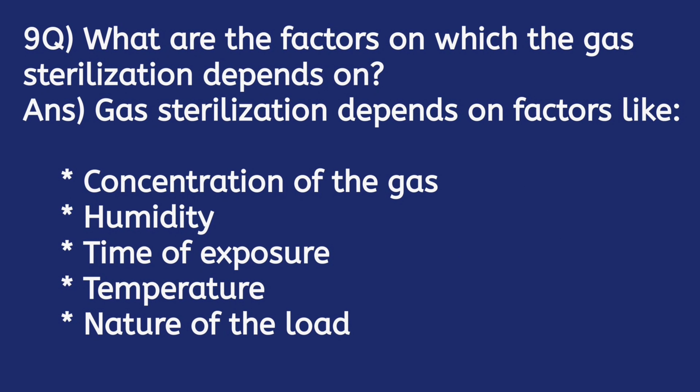What are the factors on which gas sterilization depends? Gas sterilization depends on factors like concentration of the gas, humidity, time of exposure, temperature, and nature of the load.